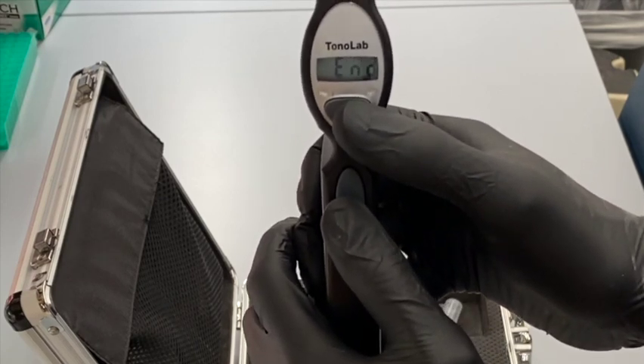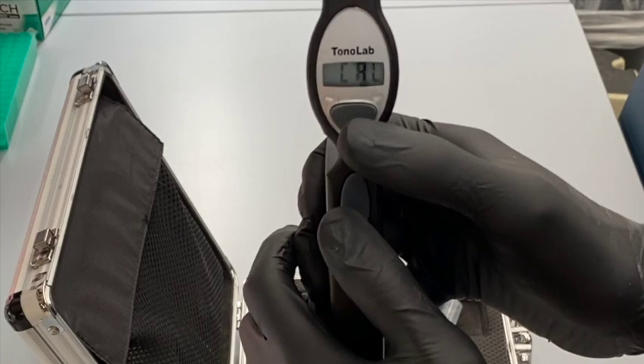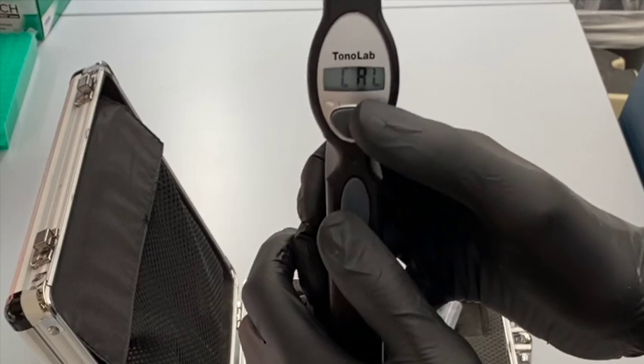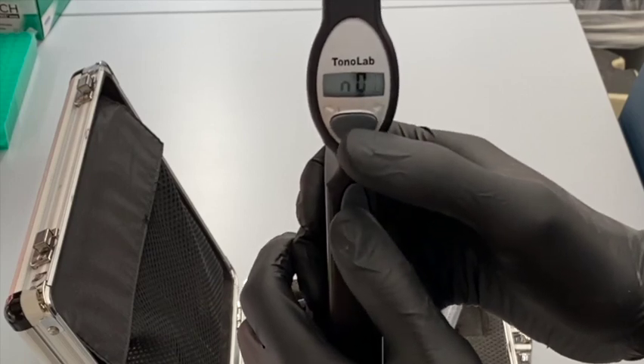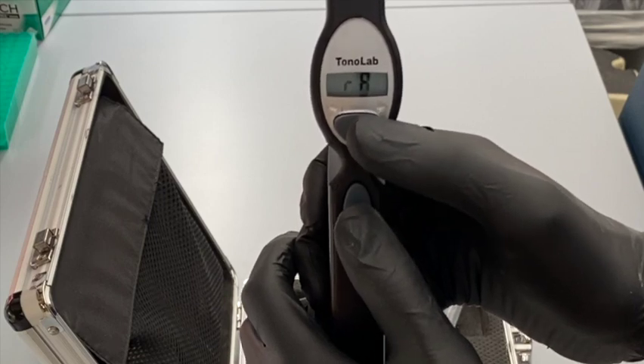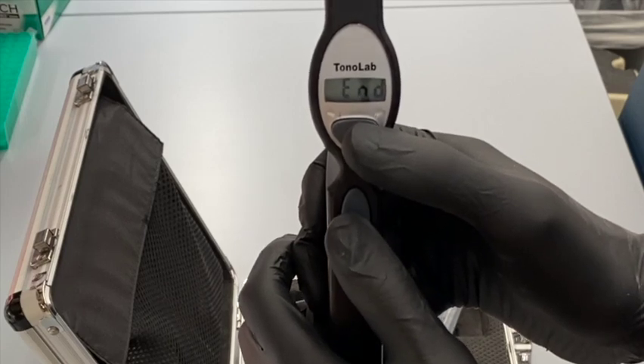The TonoLab is calibrated to take intraocular pressure measurements from both mice and rats. So if you press both buttons at the same time while on the end function, you'll reach the calibrate function as seen here. Then you can click right or left with the button directly below the display in order to toggle between mouse or rat. An N is a symbol for mouse and an R is a symbol for rat. Sometimes when new batteries are placed in the TonoLab, it will reset onto rat, and we need to make sure that we reset the machine to measure mouse intraocular pressure correctly.